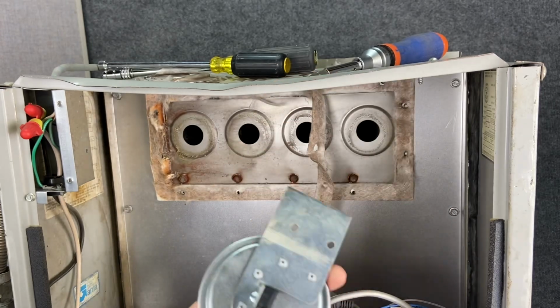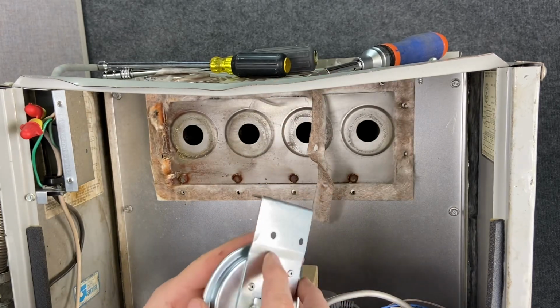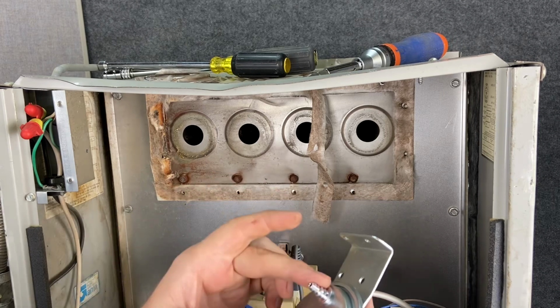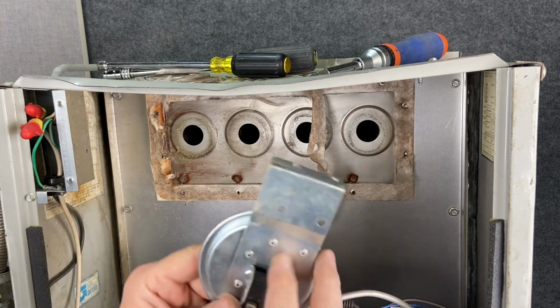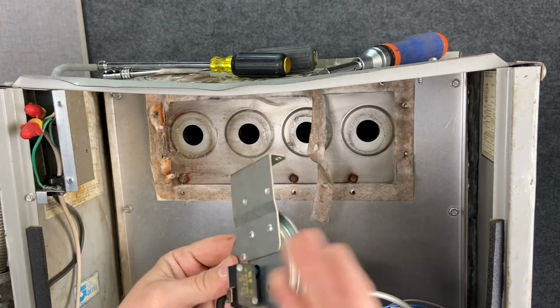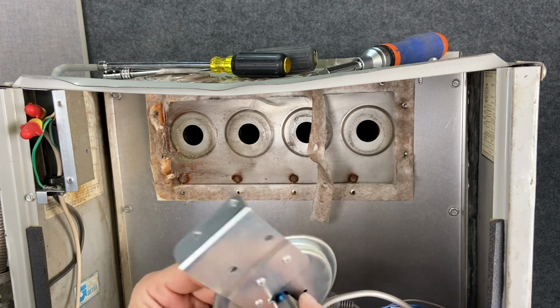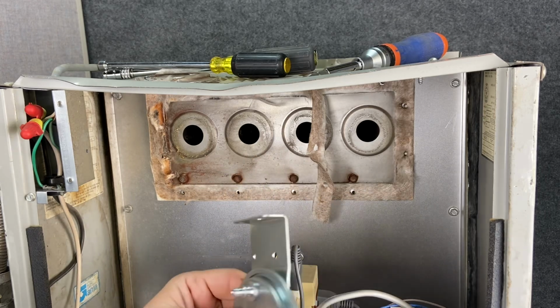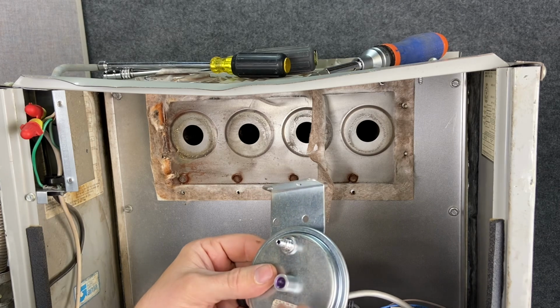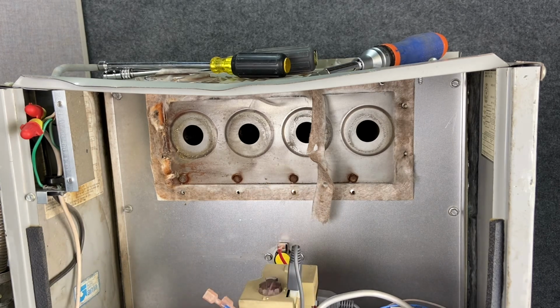Sometimes these will go bad if the furnace is leaning the wrong way and you get moisture in here, which is a whole other issue, but they'll also go bad over time. That little diaphragm that moves back and forth in here can start to crack and break over time. But you can simply check it by using a manometer, to see if it's actually closing or not, getting the right vacuum to it.